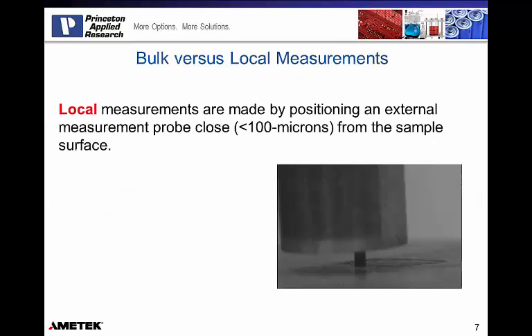So let's contrast that to a localized measurement. Localized measurements are made by positioning an external measurement probe close to the sample surface. So these are non-contact measurements. When we say close for an SECM, we're looking for about 2 to 4 probe diameters away from the sample surface. So it's non-contact, but in an example of a 25 micron probe, you want to be between 50 and 100 microns away from the sample surface. That's going to be roughly the diameter of a human hair away from the sample surface. And so a common question is how we're going to be able to position the probe that close to the sample surface without touching it. And that's going to be one of the topics we'll cover today.